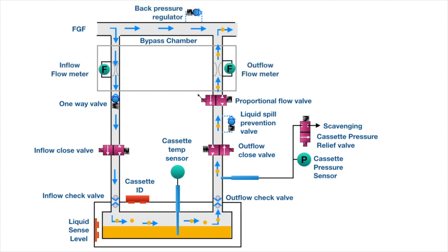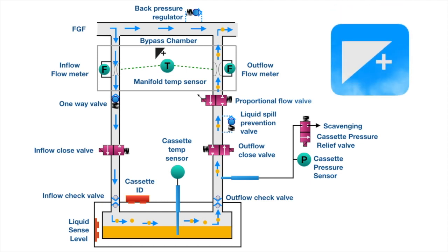Temperature compensation is achieved by the central processing unit, the CPU. The microprocessor receives input from multiple sources every 200 milliseconds, including fresh gas flow rate, carrier gas composition, set vapor concentration, liquid level, and temperature in the vaporizing chamber or sump. It controls vapor output electronically. The symbol for enhanced temperature sensing is seen on the front of the cassette in Aladdin 2 vaporizers.